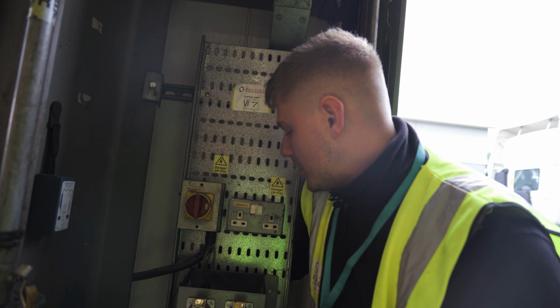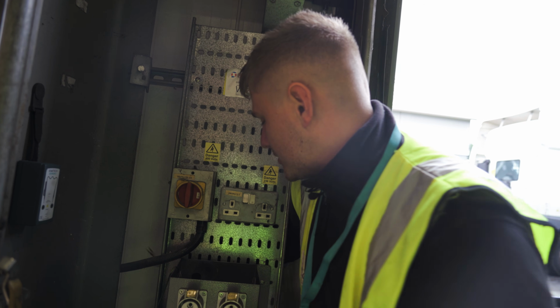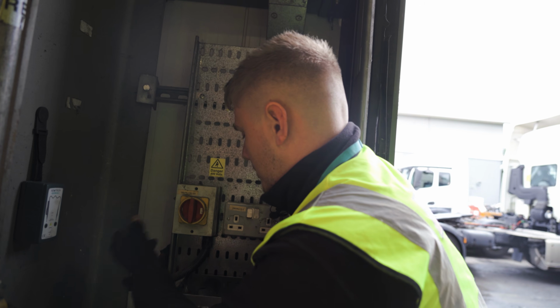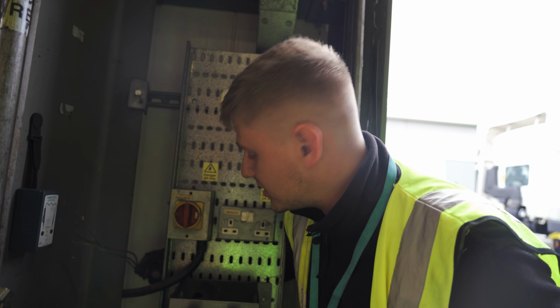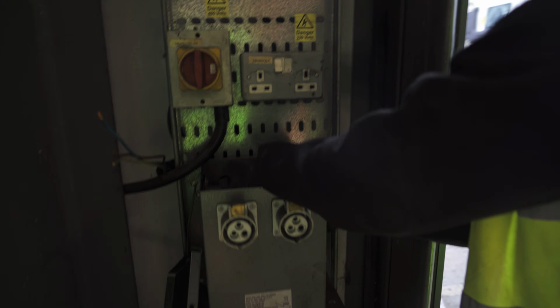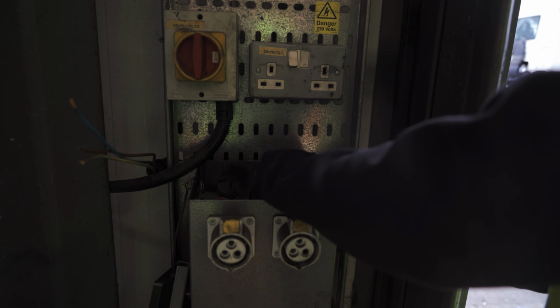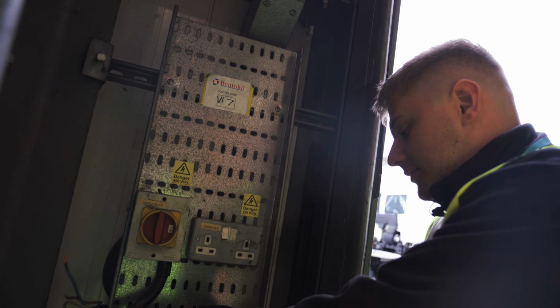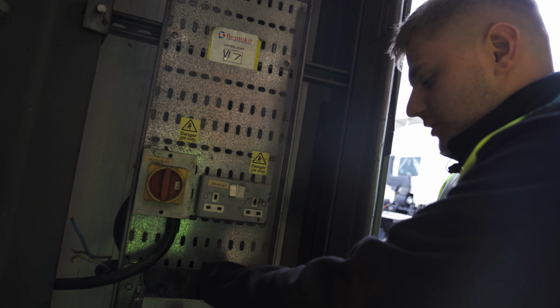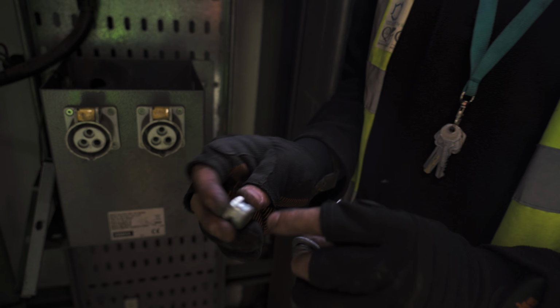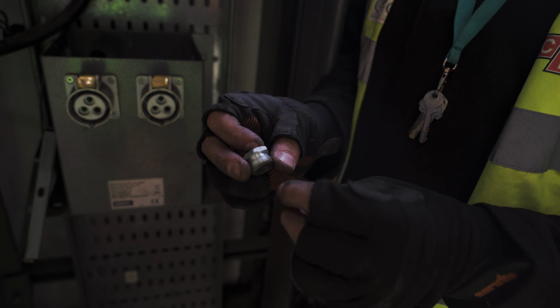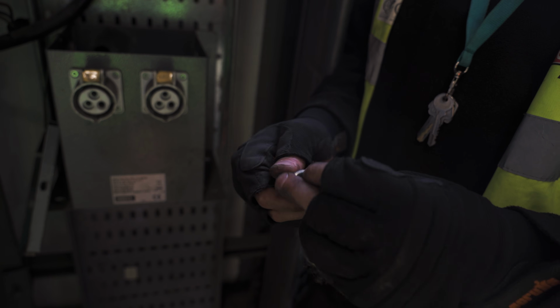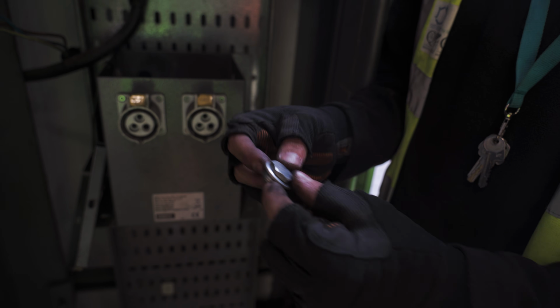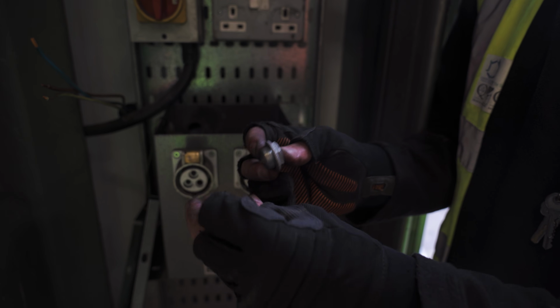It's not there yet, but those glands were pretty tough to undo, though being able to grab hold of this and spin it made it a bit easier. Like I said before, these transformers come with 2 20mm knockouts either side, which is handy, but it means if you're not going to use them, you want to cover them, and they've opted for the bung route. Now they actually had both of these lock rings on the inside, because you've got this dead bit of metal with no thread on. You do need 2 lock rings, but what I actually like to do is put one on the outside like that and then bolt it through with one.